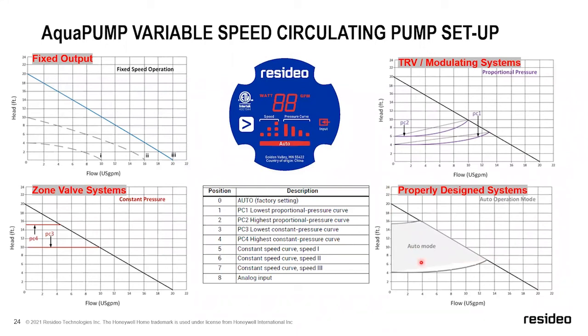So if you have this pump and you put it in auto, and let's say it's an in-floor system, and you've designed this hydronic in-floor system for 1/2-inch tubing, and every loop being, let's just call it 225 feet. But let's say you weren't paying attention and somebody went through and laid out one loop at 350 feet. The problem is this pump in auto mode, from my experience, won't find that one extraneous loop. So when I say properly designed system, that means everything's roughly designed properly, everything's roughly the same, within the same type of criteria. If you've got one loop that's creating 3 times as much head pressure, this pump is going to have a hard time finding that one specific loop. So properly designed system, auto mode, all day, every day.